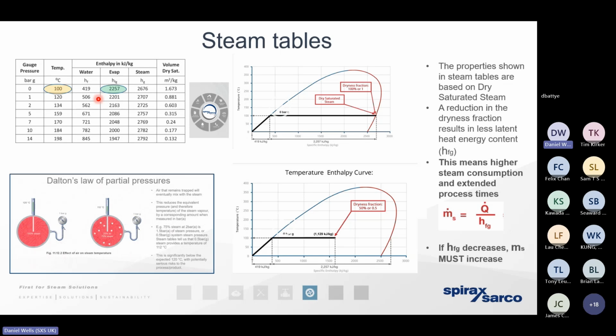So if we'd started off by calculating our client's cost of steam at the very, very beginning, if we now know that that steam is significantly wetter than expected with half the energy present that we were expecting, we now appreciate that we've got to produce twice as much steam. So of course, our cost of gas, our cost of steam, and our carbon emissions are going to increase significantly. But it also means that perhaps we've made the mistake of undersizing the steam trap. Because if the heat exchanger needs to consume twice as much steam, the byproduct is also going to be twice as much condensate. So we need to make sure that the size of the steam trap, the capacity, and the capacity of the condensate return infrastructure, has actually been sized to accommodate the mass of condensate, which is in turn based upon the condition or the quality, the dryness of the steam that the boiler is producing.